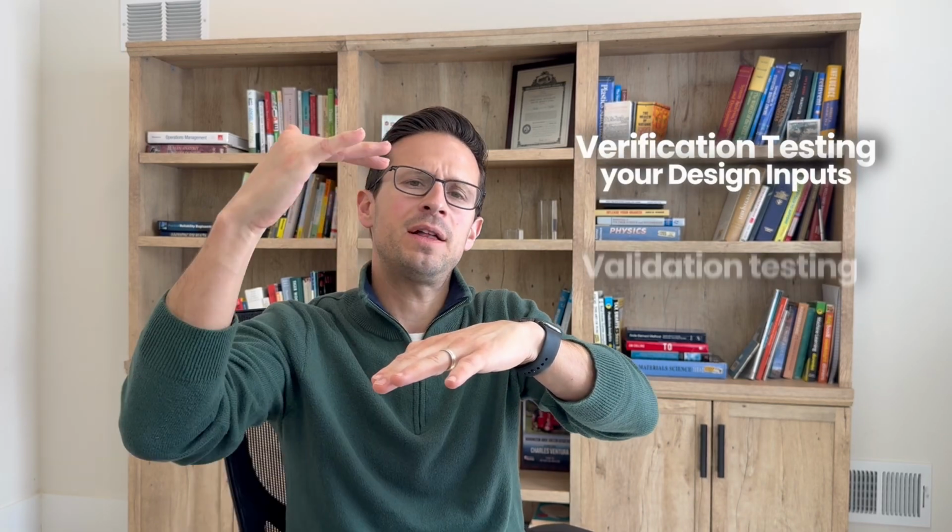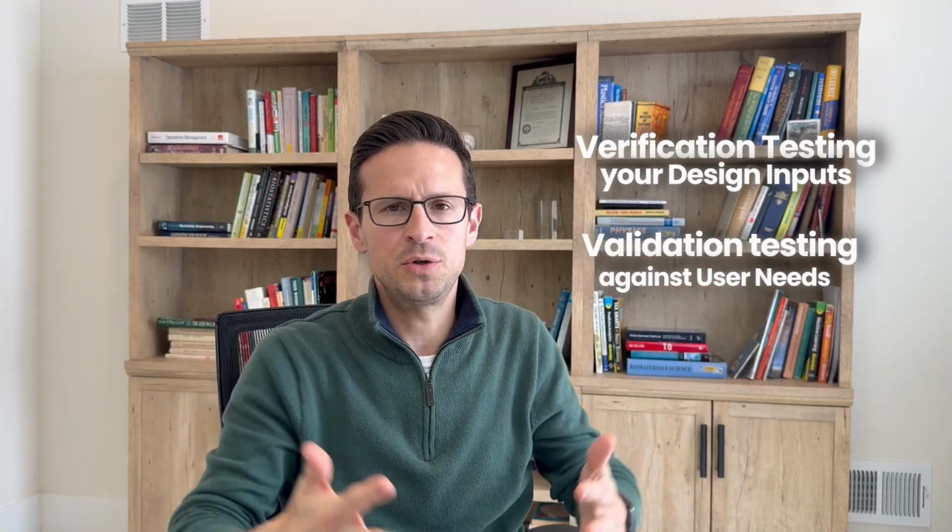So you want to be as close to commercially equivalent product as possible, and you want to justify your rationale for whatever you're doing. I think at a high level that covers verification and validation, right? Verification, testing your design inputs. Validation is testing against your user needs, usually a little bit more qualitative, and also could include human factor summative. Once you do all of that and you pass all your design inputs, you pass your user needs, pass your human factor summative, now you've reached the phase of verification and validation being complete, and that's a ginormous milestone with the product development process.